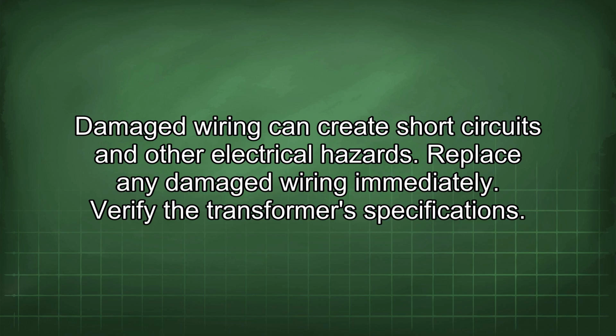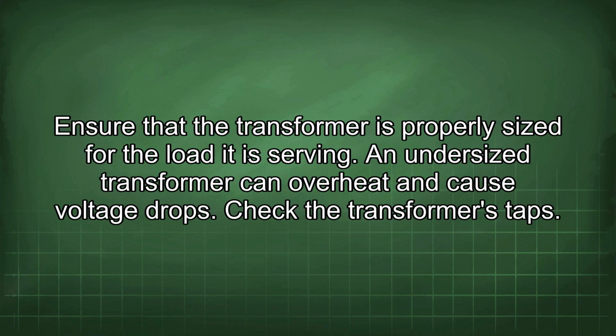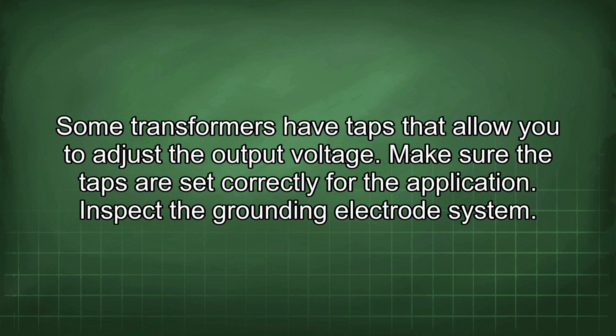Verify the transformer specifications. Ensure that the transformer is properly sized for the load it is serving. An undersized transformer can overheat and cause voltage drops. Check the transformer's taps. Some transformers have taps that allow you to adjust the output voltage. Make sure the taps are set correctly for the application.